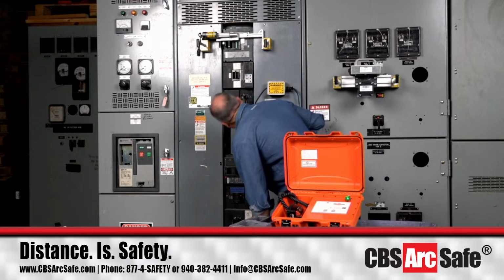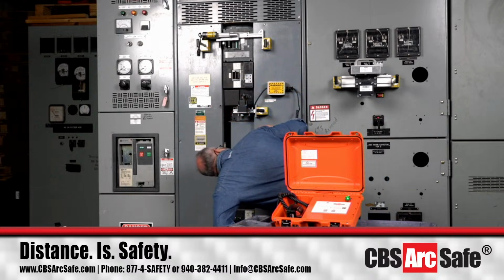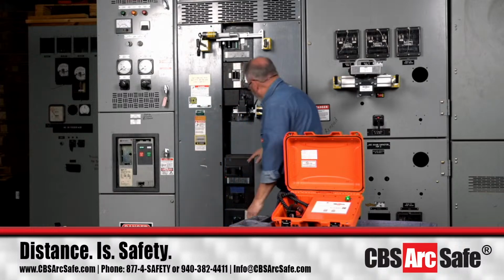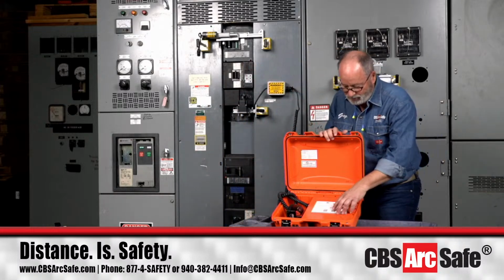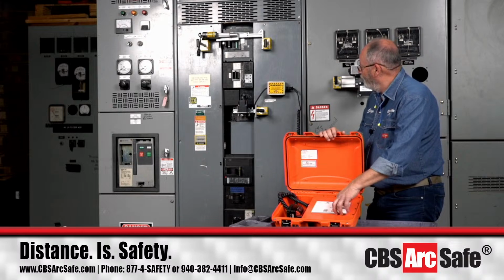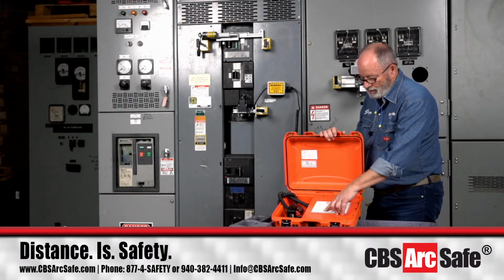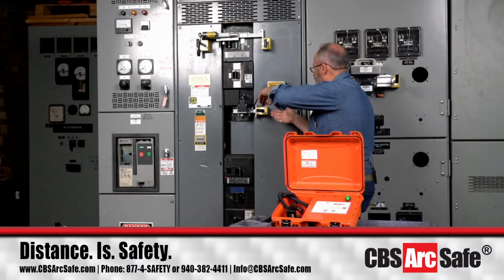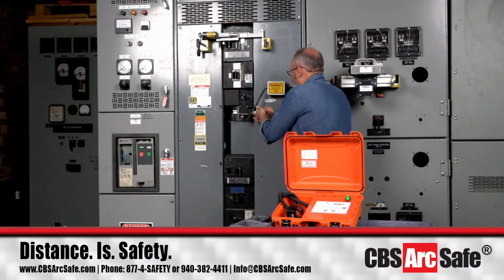Now we're going to operate the little breaker. Let me just check the position here real quick before I do this. It's in the on position, so we're going to move it to the off position. We're going to do trip first, and then close. I'm going to take this RSA off so you can just look at the bottom side of it.